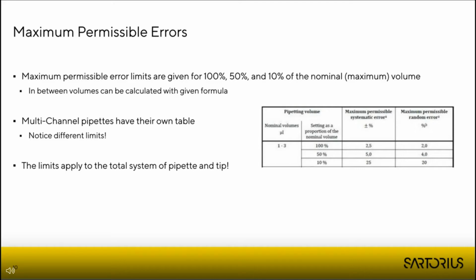And this is extremely important. These limits apply to the total system of pipette and tip. So you can't calibrate a pipette without a tip, and the tip must be specific to the calibration and what we are going to use. So let's say you have two totally different tip types and you switch from one to another, then you need to recalibrate the pipette with the new tip type.